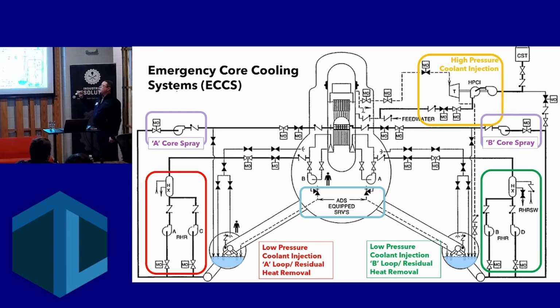But hopefully we don't have to rely on core spray systems. Next we have the low pressure coolant injection, we call it LPCI, and it is a 2-train system, but each comprises 2 independent trains itself. We draw 1 heat exchanger here, but Peach Bottom actually has 2 heat exchangers per loop. And the great thing is, we just completed a modification maybe 8 years ago to cross-connect those safety systems so that I have a lot more flexibility. If there's any one failure of a heat exchanger or a pump during an accident, I can swap over to the other one, so I get a lot more bang for my buck in terms of reactor safety.